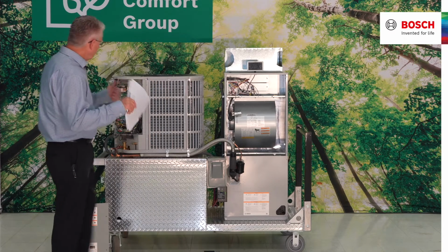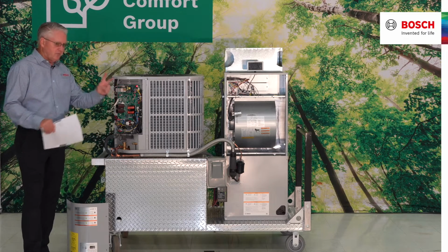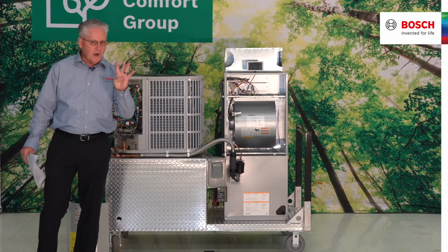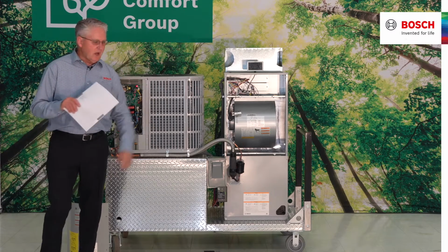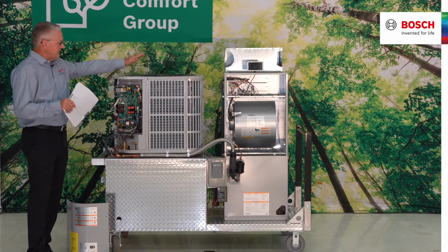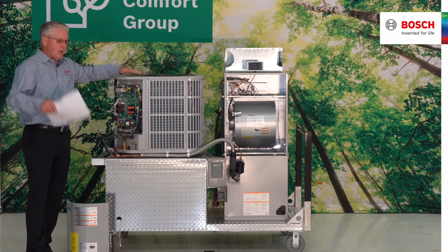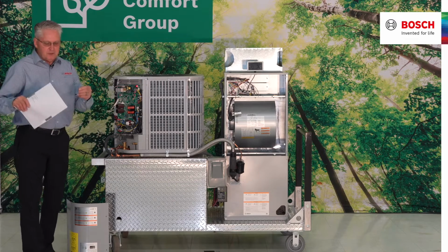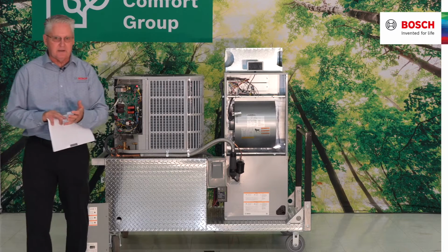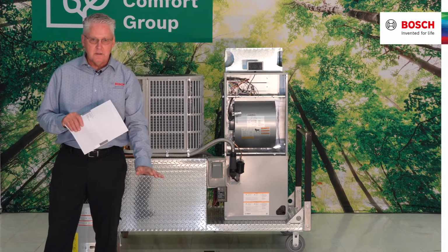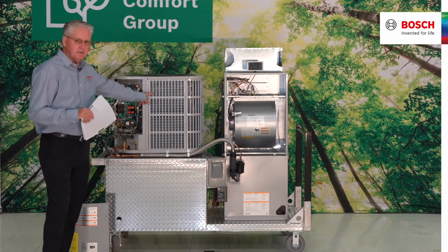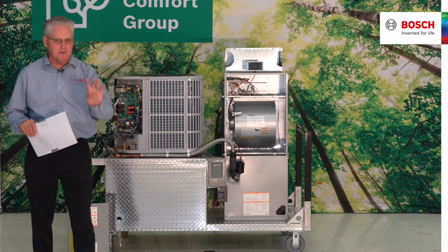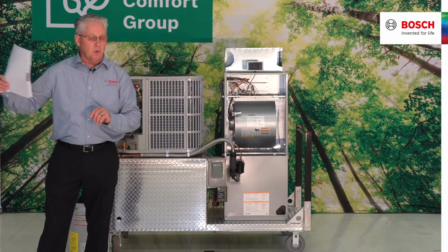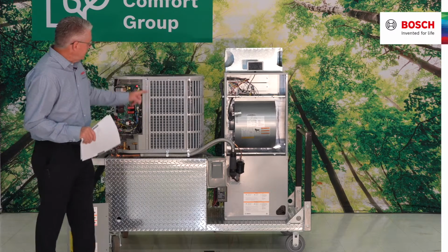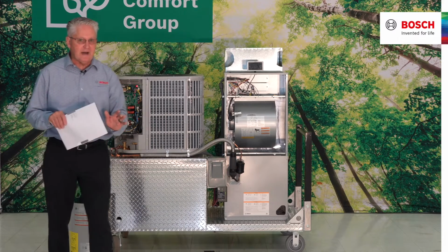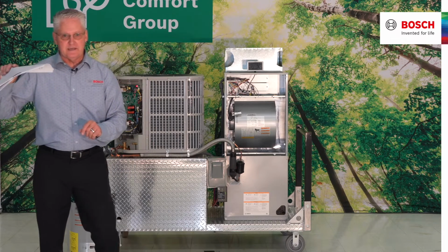And in that particular logic, we now have the capability of running 2 wires for an air conditioner, 4 wires for a heat pump. With all of that logic built into the board, I'm allowing myself to have an 11-speed condenser fan motor that ramps up and down. When I start this machine, it is basically looking at 1.4 amps and less. I'm also allowing this machine to be an air conditioner all the way down to an outdoor ambient temperature of 40 degrees, all the way up to 120 degrees, and it is a heat pump on this particular machine all the way down to +5, all the way up to 86 degrees.